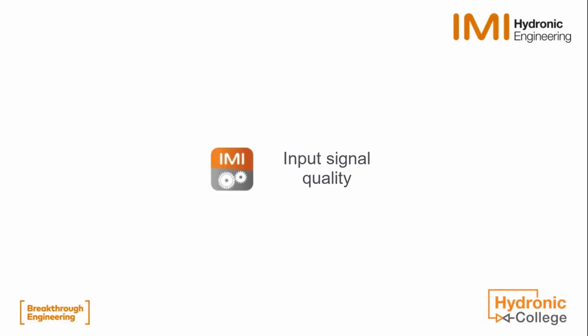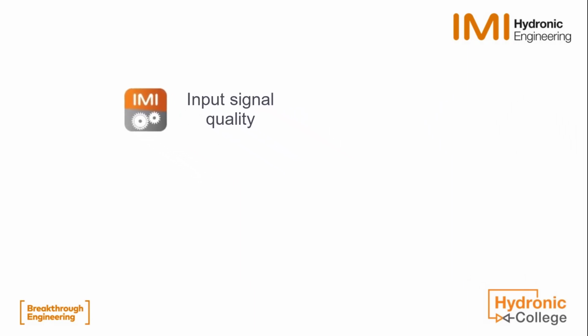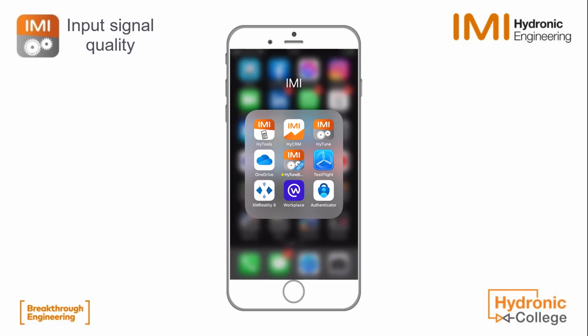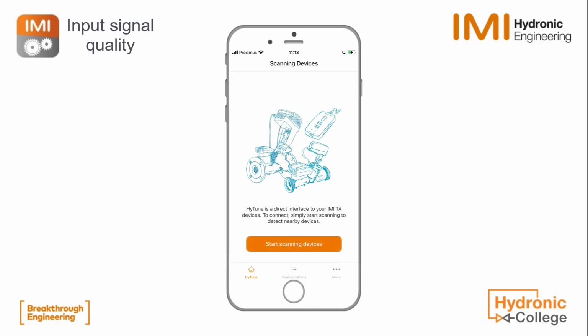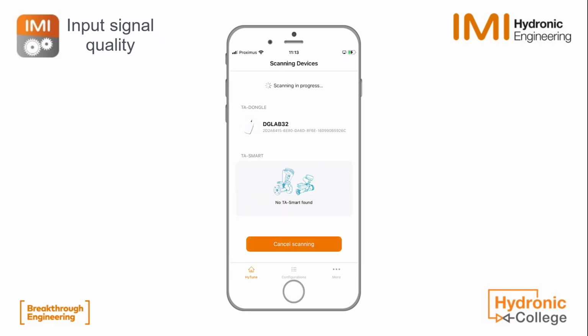A video to show you how to check the input signal quality on a TA-Slider with HyTune. This option could be useful when there is an issue with, for example, an actuator that is constantly moving or seems not able to close the valve fully.